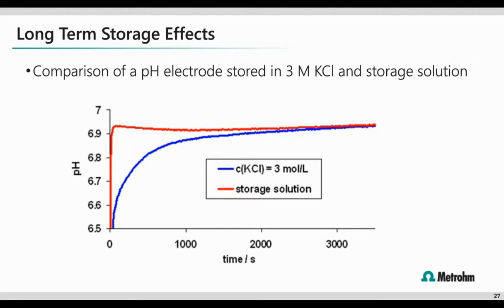If you're sitting there listening now and cringing a little bit because you've been storing your electrode in KCl, don't fret. You really will just need some front-end conditioning time to make sure that you're getting a steady and accurate signal. So get that electrode bulb stirring in water to let it refresh, and then from here on out, let's look at using an electrode storage solution.